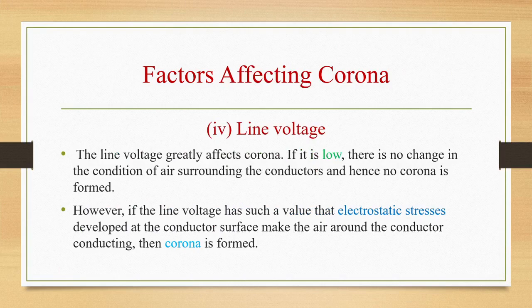Fourth one is line voltage. The fourth factor affecting corona is line voltage. The line voltage greatly affects the corona. If it is low, there is no change in the condition of air surrounding the conductors and hence no corona will be formed. However, if the line voltage has such a value that electrostatic stresses developed at the conductor surface make the air around the conductor conducting, then corona will be formed.